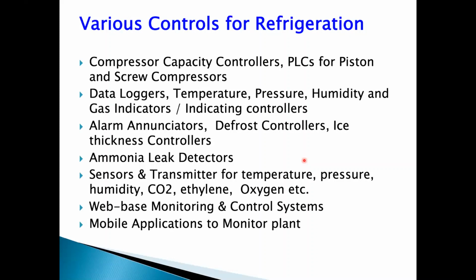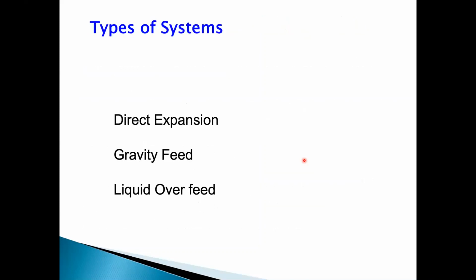We need to have defrosting systems. In ice bank tanks, we need to measure the thickness of the ice and operate the ice thickness. Of course, for the safety part, we need an ammonia detection system, the most important thing. And as I told you, for monitoring different parameters, we need sensors. Nowadays, we have a lot of plants which have automation systems available, from a very basic level to a very high-tech level, which can be monitored and controlled through your mobile. You can have centralized systems. So this is all about what we need to have or what we have. Now let's see the typical systems which are used in ammonia refrigeration systems.